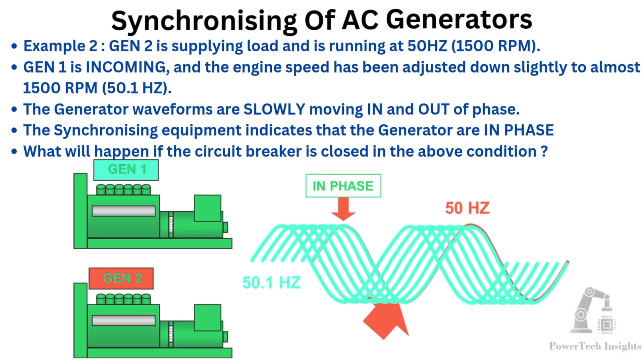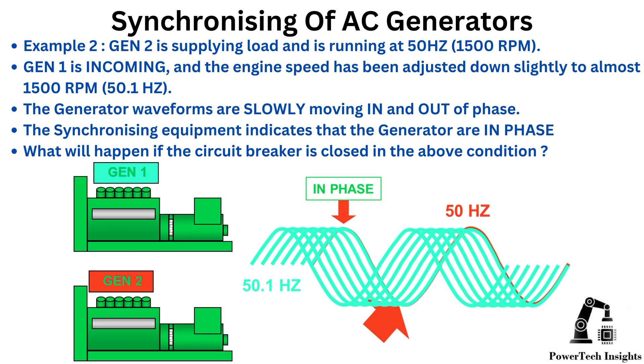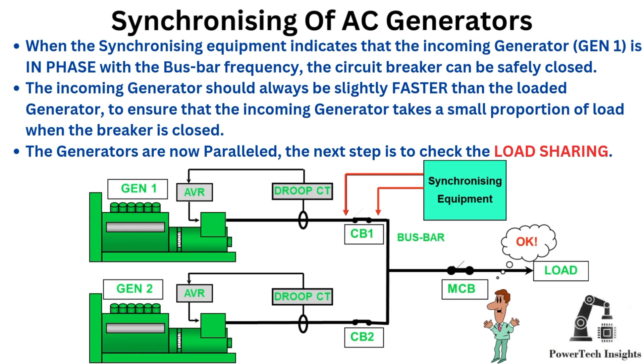Example 2: Gen 2 is supplying load and is running at 50Hz, 1500 RPM. Gen 1 is incoming, and the engine speed has been adjusted down slightly to almost 1500 RPM, 50.1Hz. The generator waveforms are slowly moving in and out of phase. The synchronizing equipment indicates the generators are in phase. When this occurs, the circuit breaker can be safely closed. The incoming generator should always be slightly faster than the loaded generator to ensure it takes a small proportion of load when the breaker is closed. The generators are now paralleled; the next step is to check the load sharing.